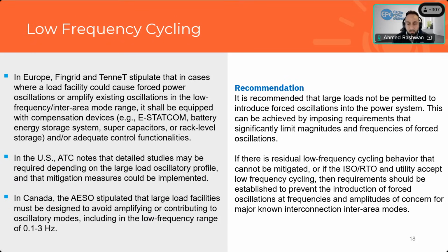Introducing rack level storage to also help smoothen out the curve, and even facility level storage as well for larger facilities to help balance overall how the facility is behaving. And what they found in that paper is it's quite effective when you combine those different approaches together, and they actually recommended looking at implementing a combination of those to really manage the load profile.